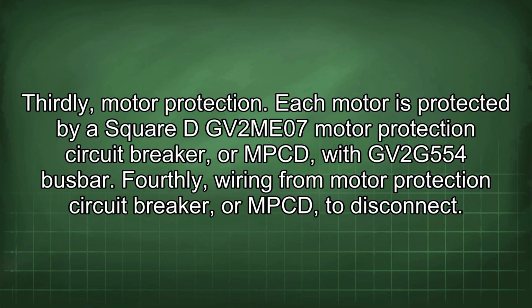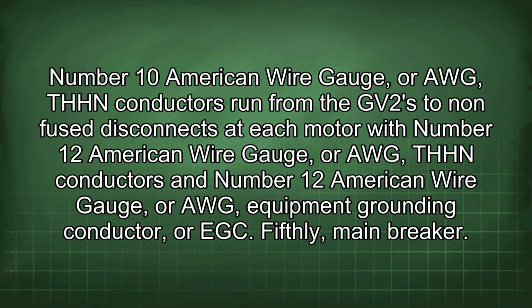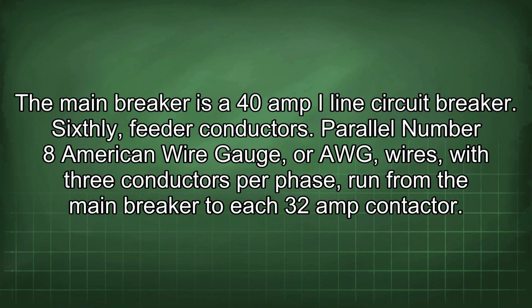Fourthly, wiring from motor protection circuit breaker, or MPCB, to disconnect. Number 10 American wire gauge, or AWG, THHN conductors run from the GV2s to non-fused disconnects at each motor, with number 12 AWG THHN conductors and number 12 AWG equipment grounding conductor, or EGC. Fifthly, main breaker. The main breaker is a 40 amp I-Line circuit breaker.